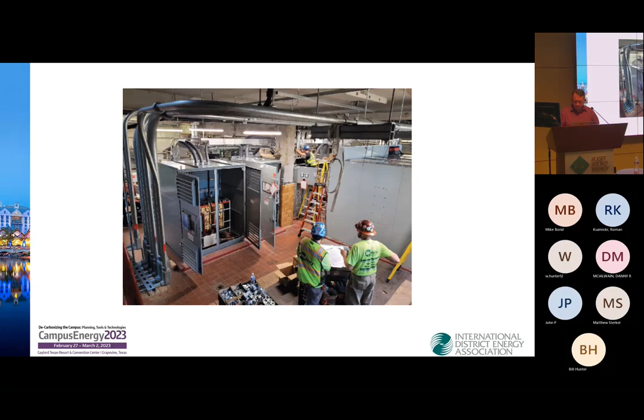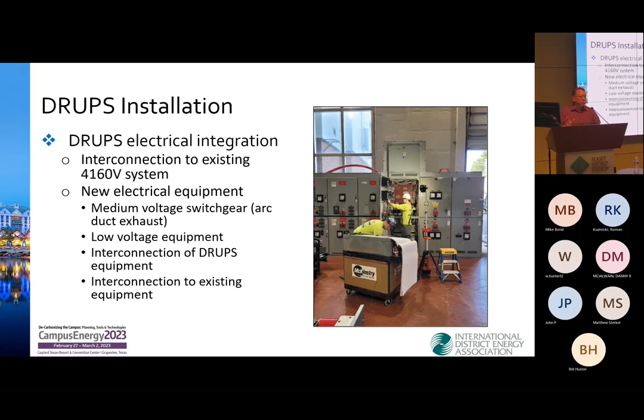Now, the tricky part is taking our new DRUPS system, which was a 2 megawatt, 4160 volt AC machine, and integrating it into the existing plant electrical system. So that's an image of McKinstry's electrician tying in the new system. And of course, when you do that, the relays have to be reset. You've got to do a coordination study, but surprisingly it was a smooth project - it went really well, and the connections are all done.